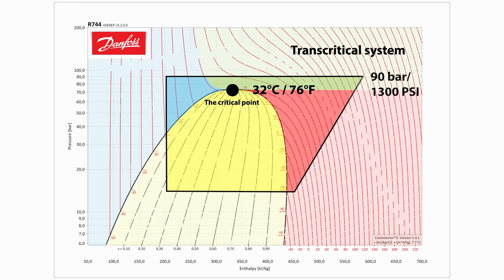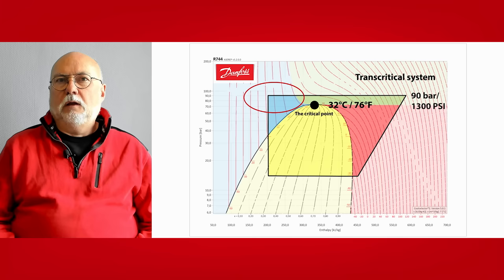Above the critical point, the refrigerant, the CO2, is not capable of condensing, changing phase back, so to speak, to the liquid phase because of the high pressure. And that gives us a few problems.